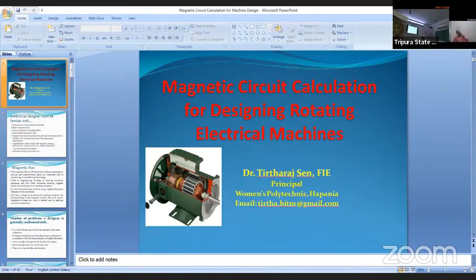Current passing per unit area in the conductors, and temperature, are very important factors limiting design, along with insulation, mechanical properties, efficiency, and power factor. So these are the limitations of design. We have to think about all these factors while designing electrical machines.